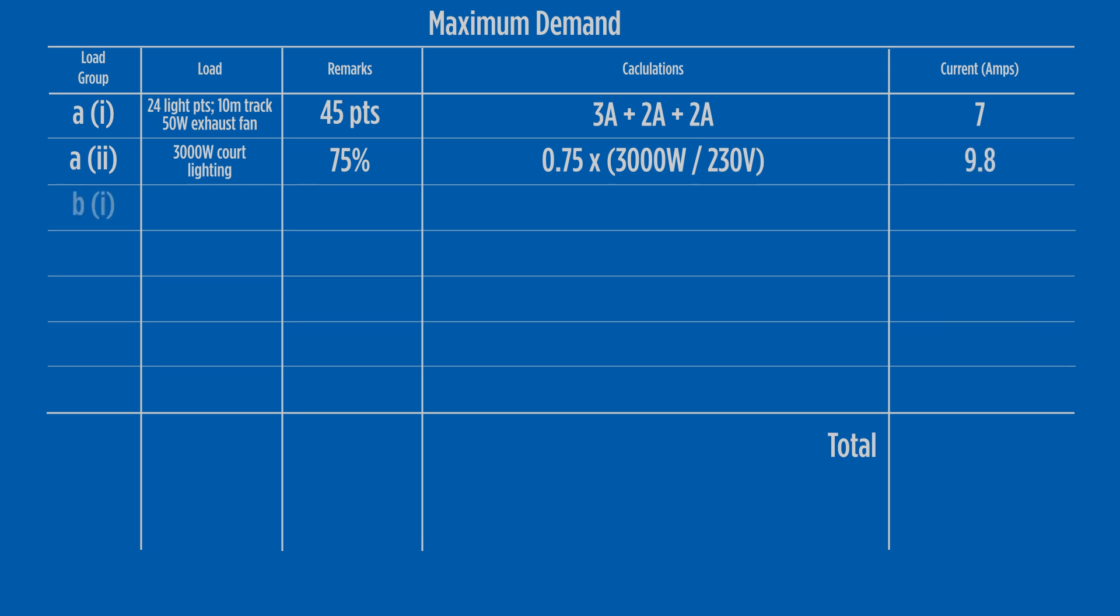Load group B1 has 9 single and 8 double socket outlets. Reading note 8 of table C1 explains that multiple socket combinations equal the number of integral sockets in the combination. This will give a total of 25 points. However, there is a 1000 watt strip heater in the installation that, according to note 9, can be included in the load group B1.